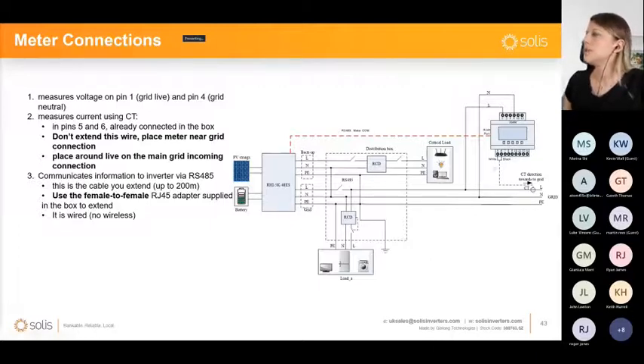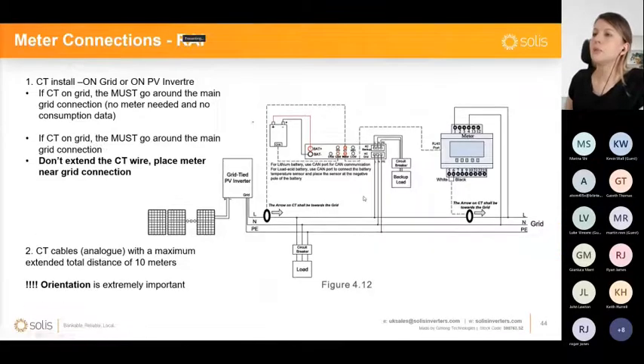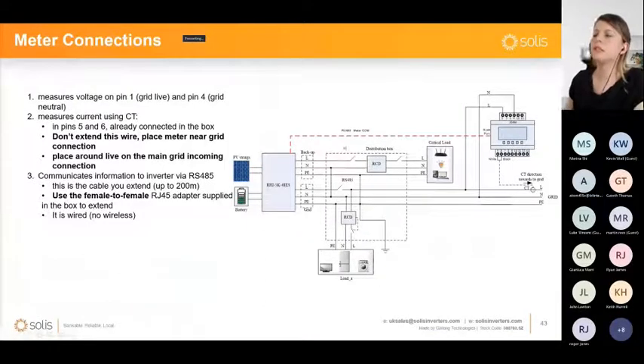As I mentioned, it's very important for that CT clamp cable to not be extended. You can extend this one, though, up to 100 meters without any problems. Sometimes if you double up the pairs, you can even go up to 200 meters. And no, there's no option for a wireless meter for now, so everything needs to be cable connected. These are the meter connections for the hybrid inverters.